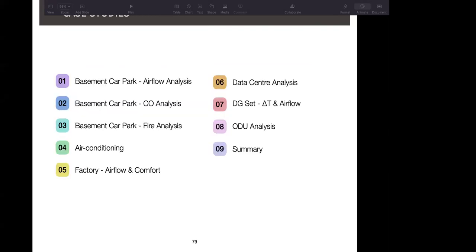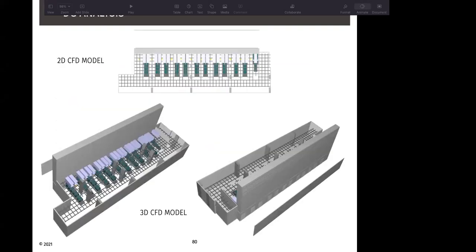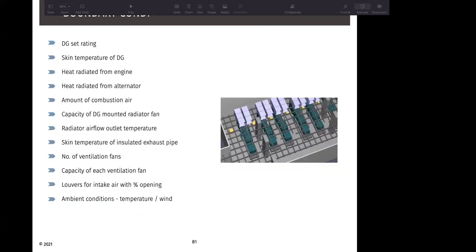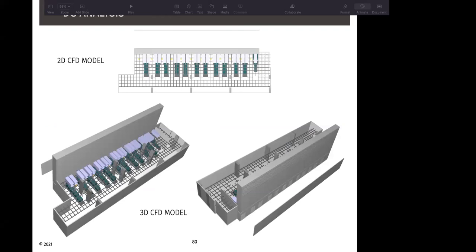Looking at the next case study, for a DG set delta T and airflow analysis, we have a DG room with 12 DG sets placed. The 3D model shows, in purple, 2 ventilation fans dedicated to each DG set, mounted right above. There is a sort of plenum, a wall created behind, for getting the supply air inside the chamber, and the exhaust is at the bottom side of that same shaft. So what we wanted to study is whether there would be short cycling of hot air from the exhaust point into the intake side, and then whether it would be pulled into the DG room through those ventilation fans.